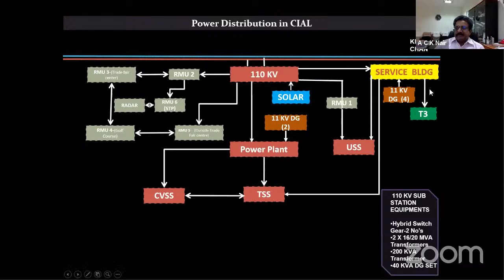So main power, this has already been explained. Other features: we have a standby power generator also, because in all airports we should have power in case of a breakdown of the main power. You should have power within 15 seconds. So we have an 11 kV generator set, DG sets with AMF, automatic main failure facility, which is able to take over and transfer the power within 10 seconds.